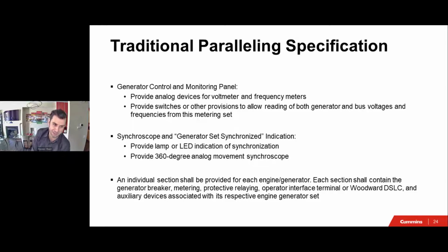So for the traditional paralleling specification, the things that jumped out at me, as you can see in here, it says generator set control and monitoring, provide analog devices for voltmeter and frequency meters, provide switches or other provisions to allow reading for both the generator set and the bus. And then I saw things calling for 360-degree analog movement for the synchroscope, sync lights, and then it asked for an individual section for paralleling controls for every generator and a master level control.